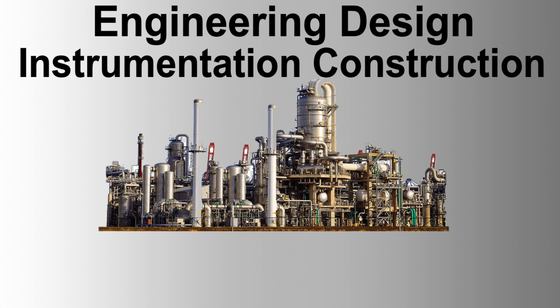All level instruments shall have connections to the vessel or a standpipe. Connections to process piping are not permitted. The connections shall be located such that impingement from process streams flowing into the vessel is prevented. Where necessary, this shall be achieved by installing deflection plates in the vessel.